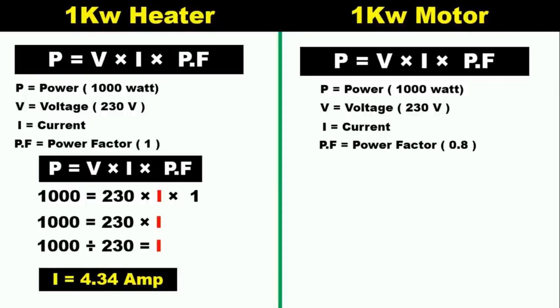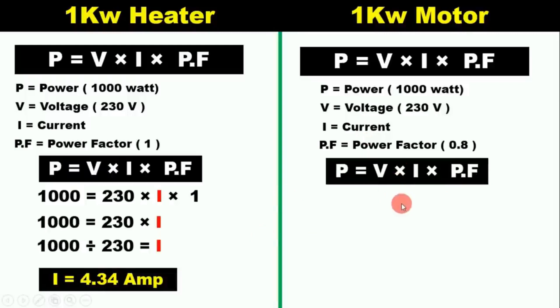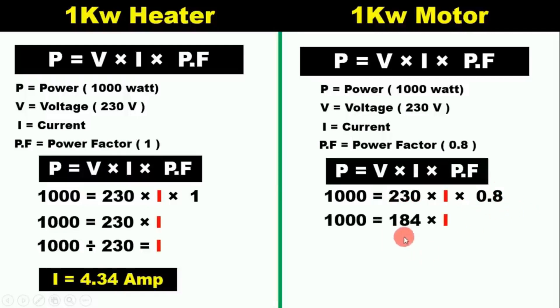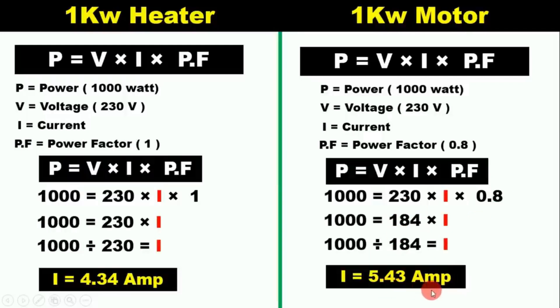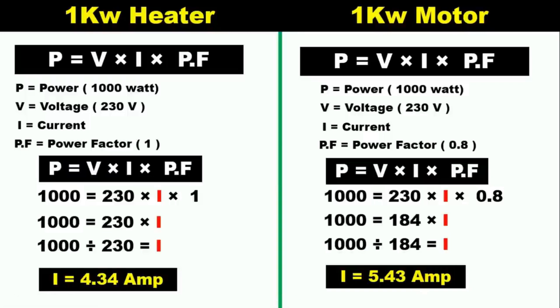Now putting all values into the formula: 1000 equals 230 into I into 0.8. When we multiply 230 by 0.8 the answer is 184. Now divide 1000 by 184 — the answer is 5.43 ampere. So you can see the difference: the 1 kilowatt heater with power factor 1 draws 4.34 ampere, while the 1 kilowatt motor with power factor 0.8 draws 5.43 ampere. The value changed due to the different power factors, meaning the motor consumes more current and the heater consumes less.